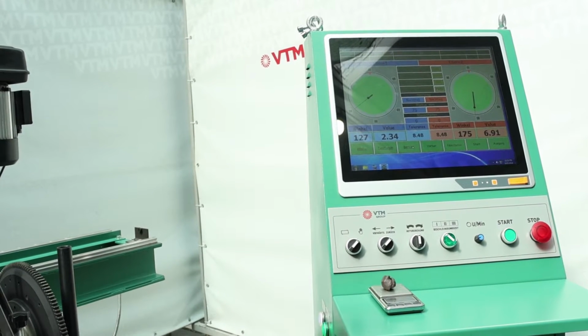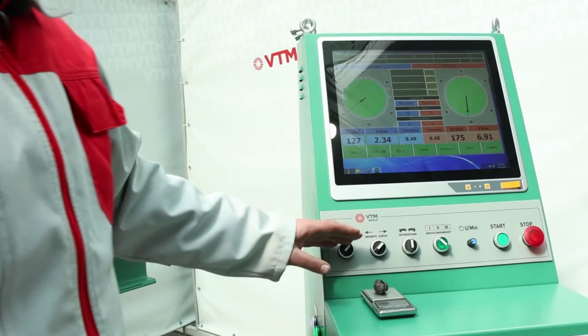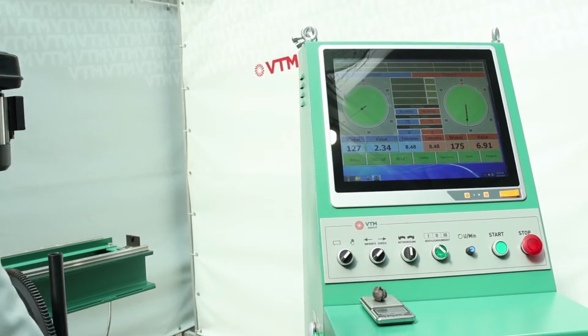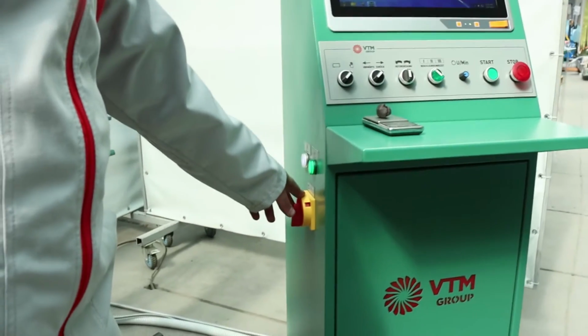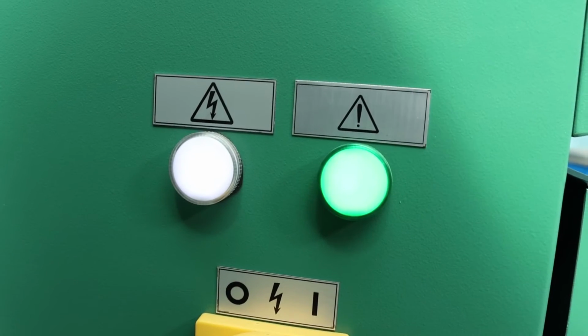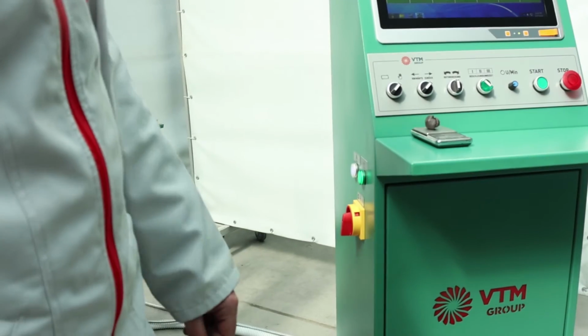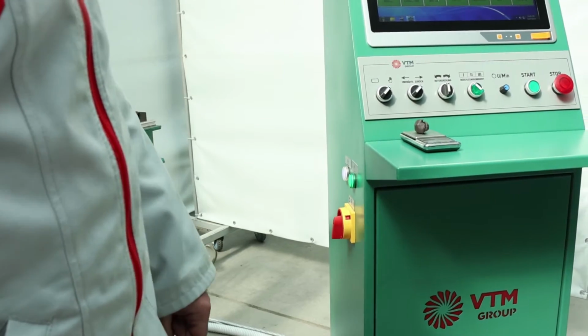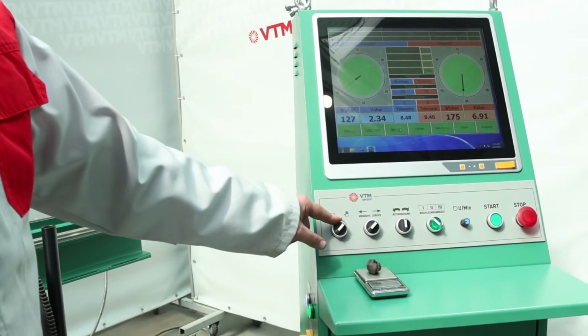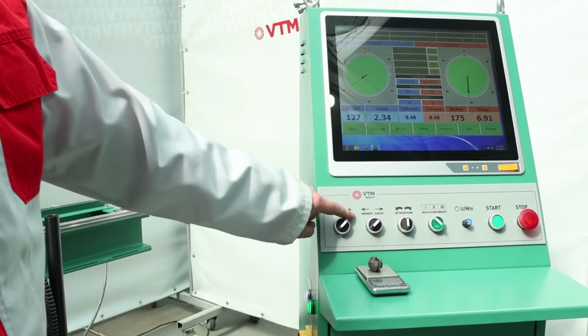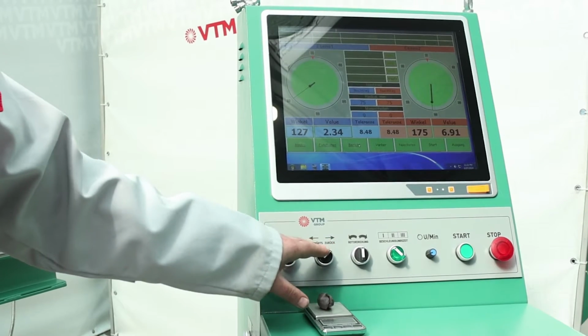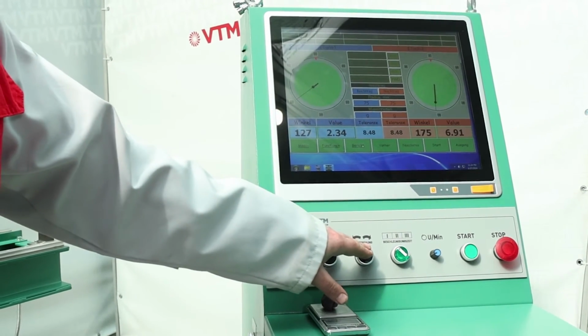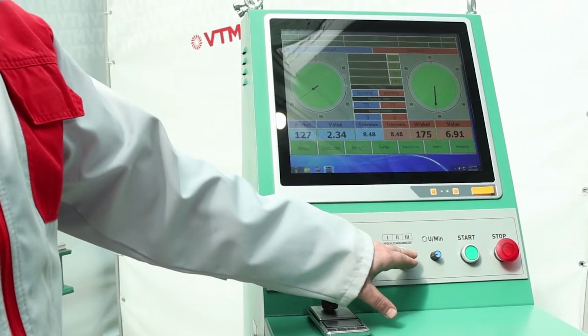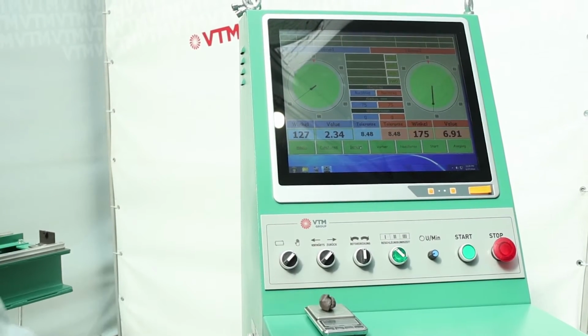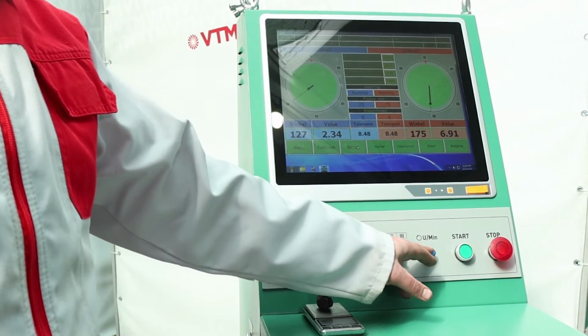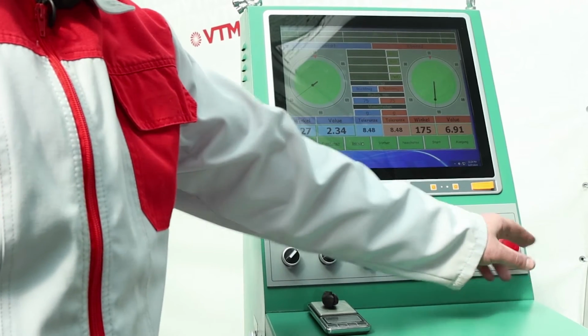So, the control cabinet consists of a housing, a panel with control buttons, and an industrial computer. A power switch and 2 lamps are provided on the side panel of the cabinet to signal the presence of voltage and the readiness of the drive. On the main push-button panel there are switches. The leftmost one is responsible for selecting the operating mode. It can be either manual or automatic. The direction of rotation of the rotor. Rotor acceleration intensity, a 3-stage switch. Rotor speed selection. Rotation start button and rotation stop button.